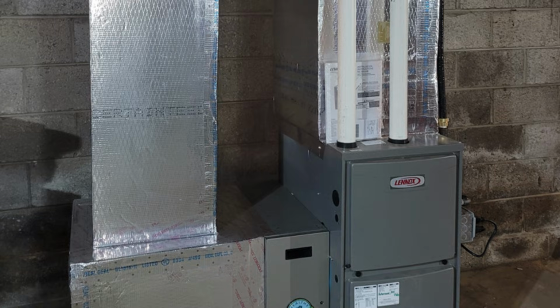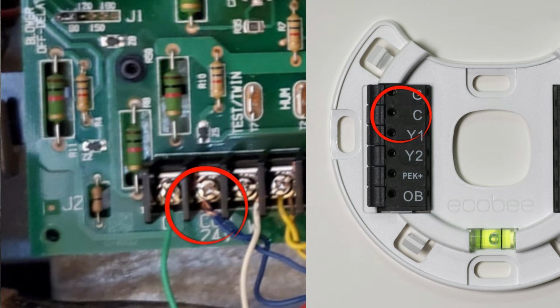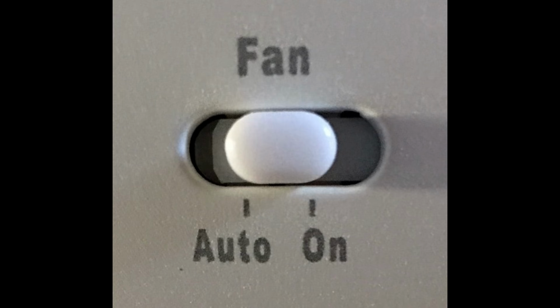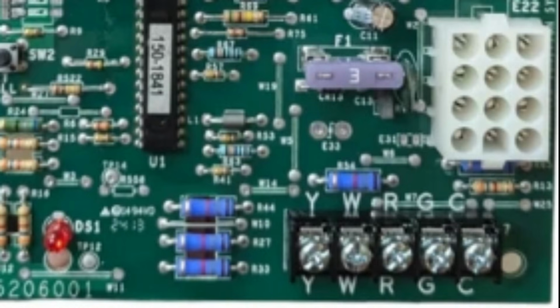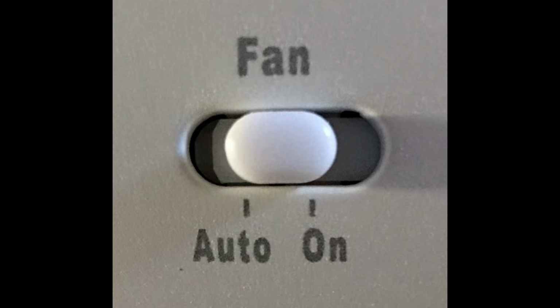That allows you to circulate air throughout the house in between cooling and heating modes. Now, if you just have a forced air furnace and no air conditioning, you can move that wire over to common at both ends, both at the control board and the thermostat, and it should work just fine because in furnaces, the control board is typically what controls the blower motor, not the thermostat. So in that case, you would only be losing the fan auto on circulation function. If you do have air conditioning hooked up, one thing a lot of people do is run a jumper between Y and G at the control board inside the unit. So if the unit gets a call for cooling, that 24 volts will jump off the Y terminal to the G and also activate that G terminal without it having to come to the thermostat. At that point, you can then move both ends of that wire to common and use it. And once again, you'll only lose that fan auto on circulation function.